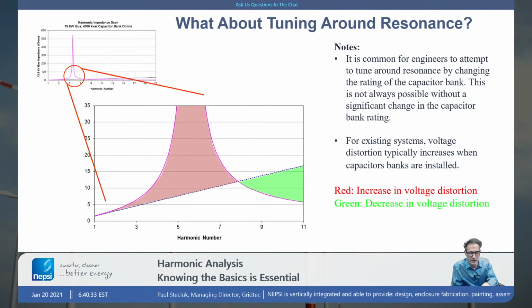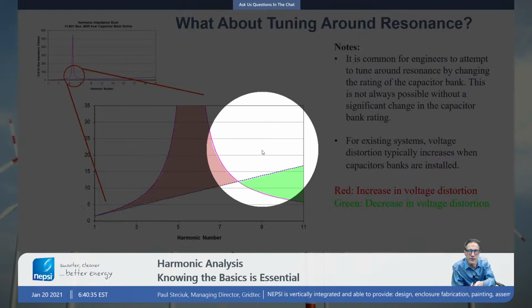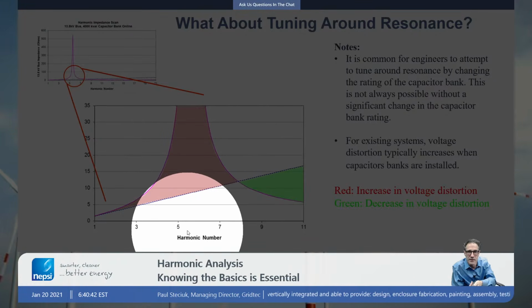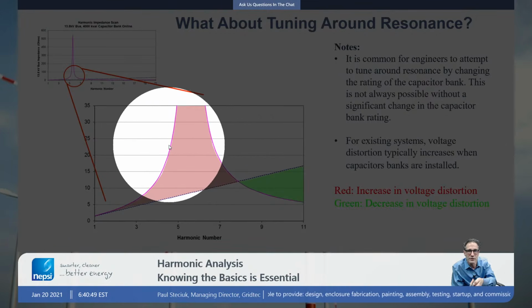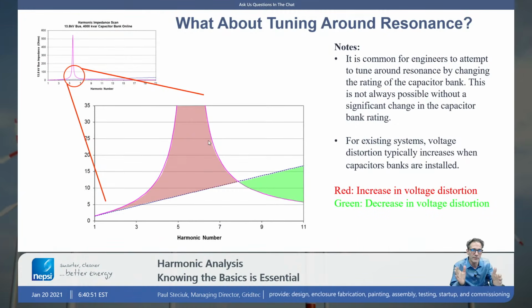The reality is that doesn't work. And the reason it doesn't work is that resonance has a certain broadness to it. It's pretty broad here. So even though I'm not over the 5th harmonic, I'm still raising the impedance across a range of harmonics. It's got a width to it. And the width of that impedance curve, the shoulder, the width of it, will vary depending upon the value of R, the resistance of a network. And that's an unknown value to some degree.